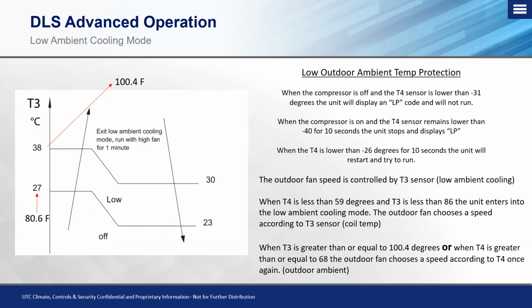With low ambient temperature protection, when the compressor is off and the T4 sensor is lower than -31, the unit will display an LP code and will not run, which essentially means the outdoor temperature is too low for the system to run. It's going to shut it off. If the system is running and the T4 sensor remains lower than -40 for outdoor temperature for 10 seconds, that unit will stop and display the LP code, which essentially says, hey, it's too cold, I can't run. It has a hard shutoff.